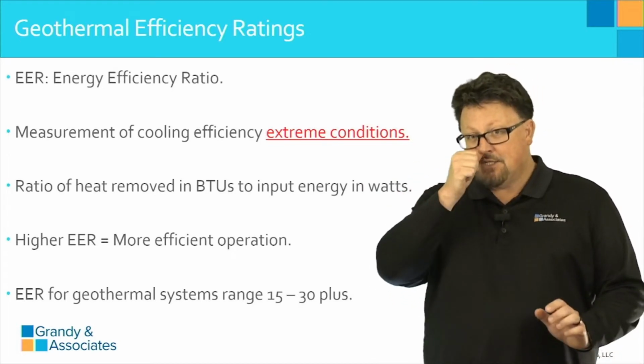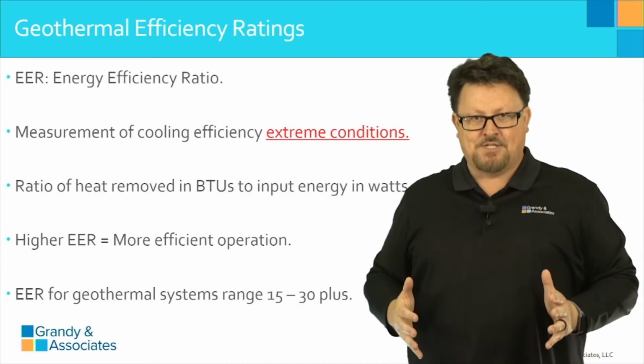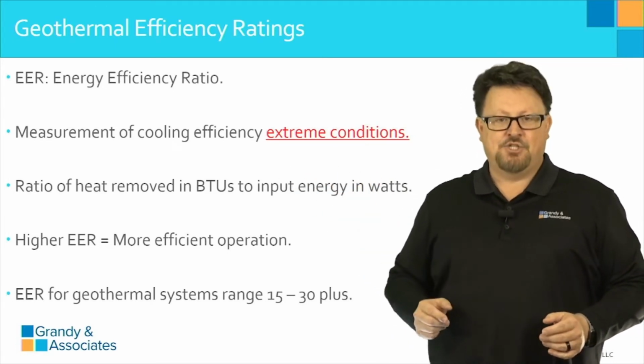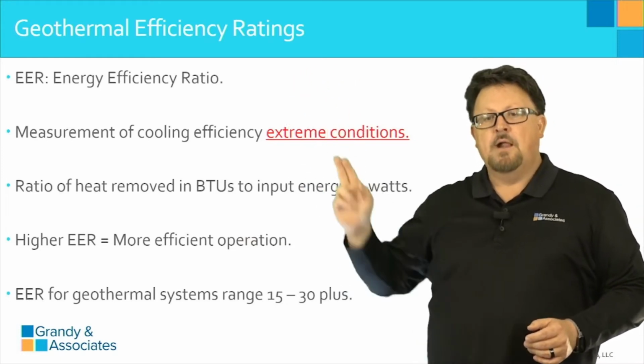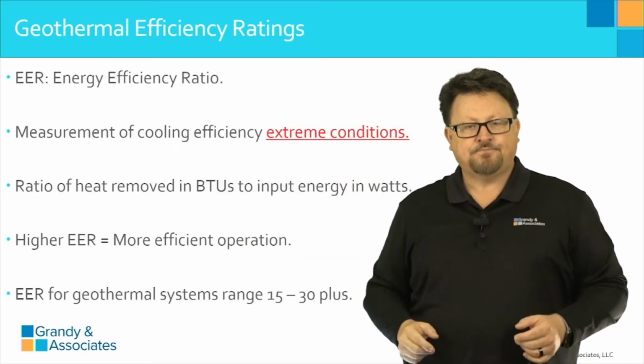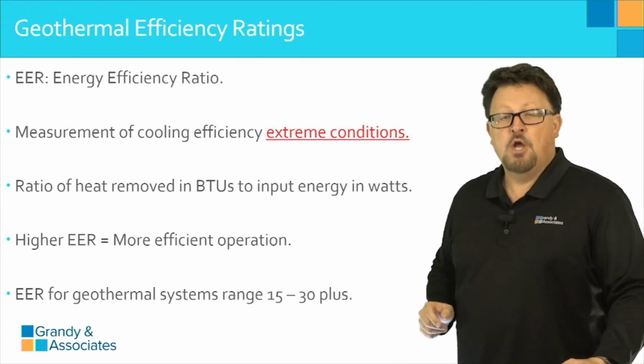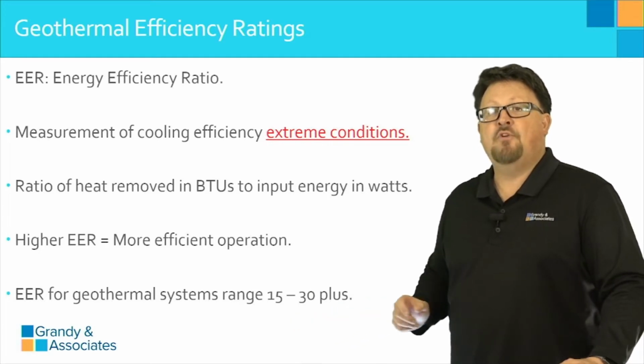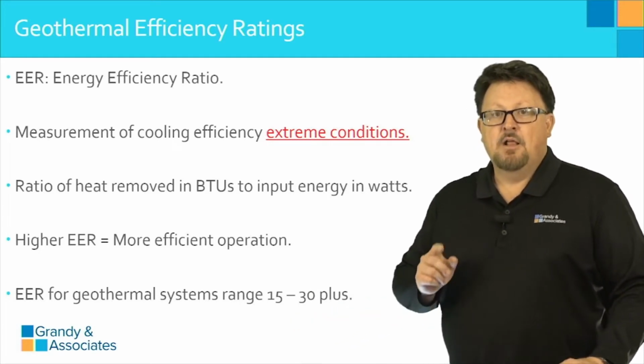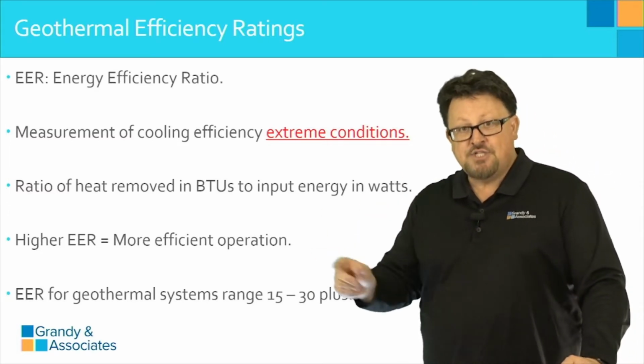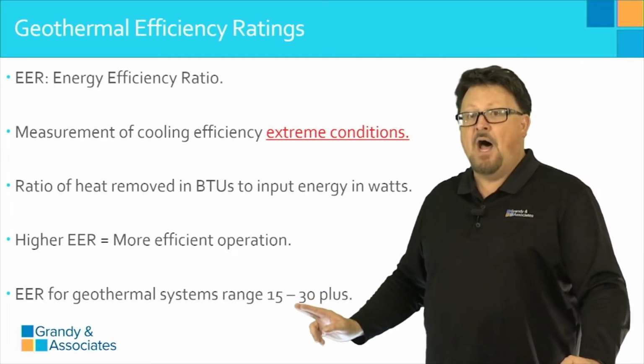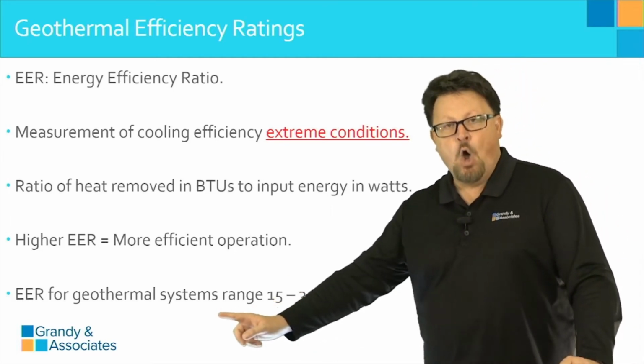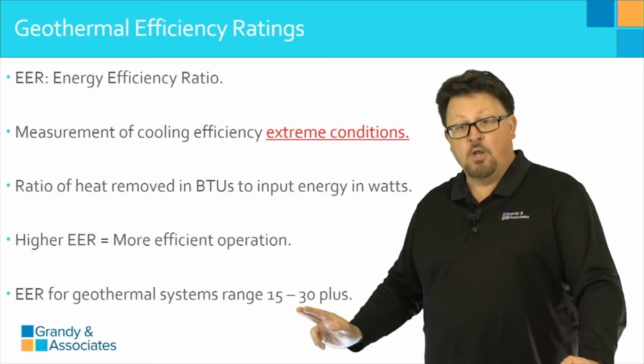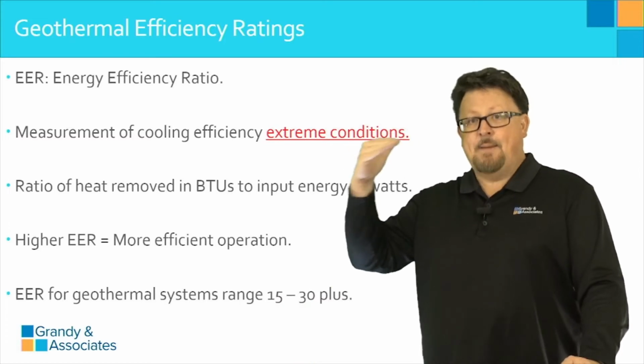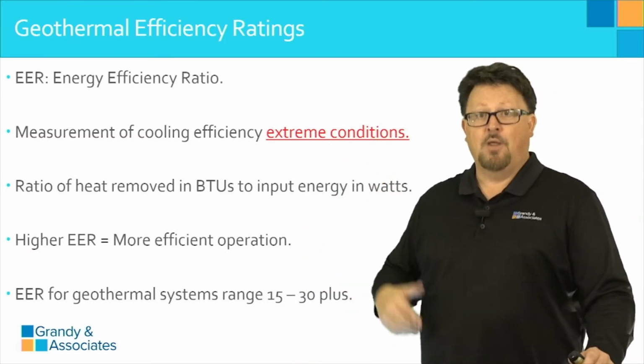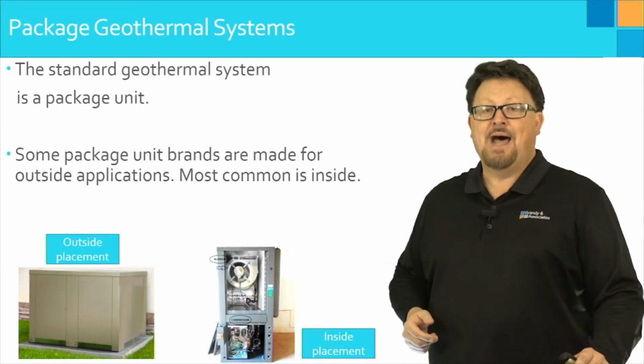So the goal of this is to determine how well the cooling part of the system is going to perform in that condition. The higher the EER number, the more efficient the operation of the system. EER scores for geothermal range from 15 to over 30. To give you an example, the split systems that we looked at to begin our study tap out at around 15 or 16 on the EER table. Geothermal begins where they tap out. And we'll show you in this section on geothermal how it is able to score so much higher.